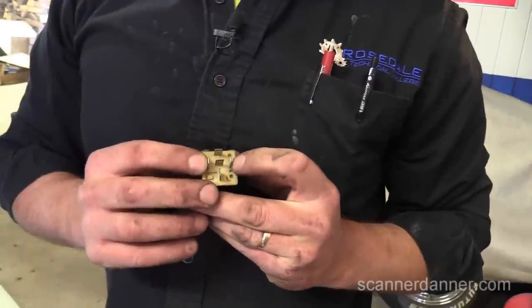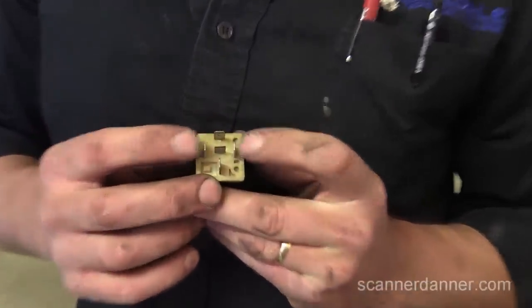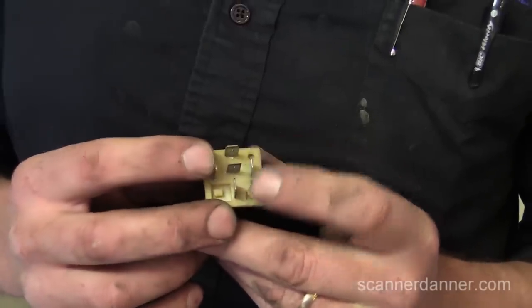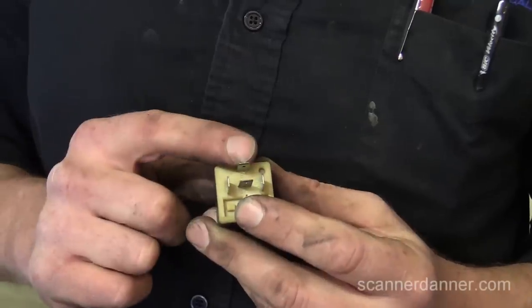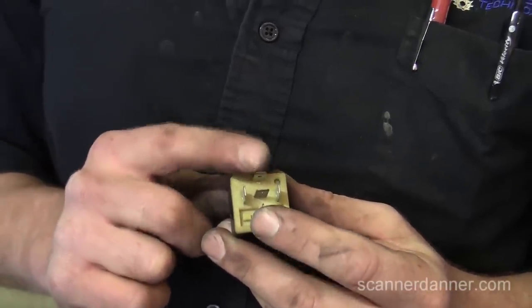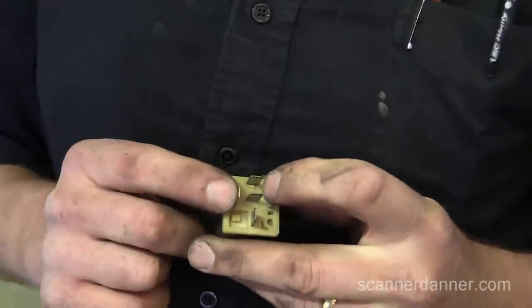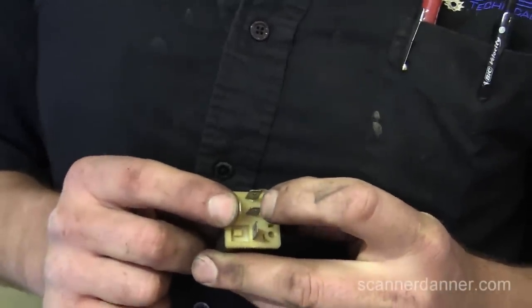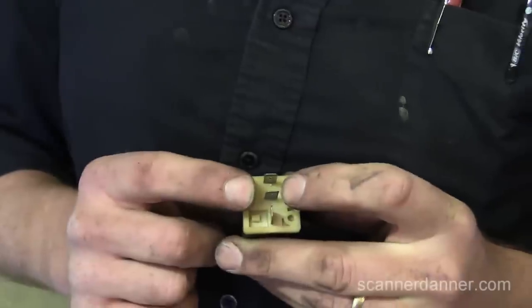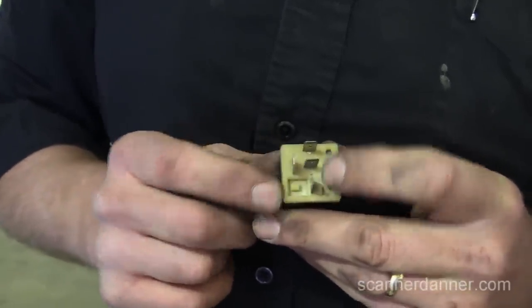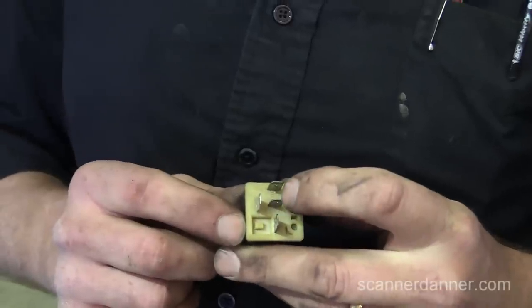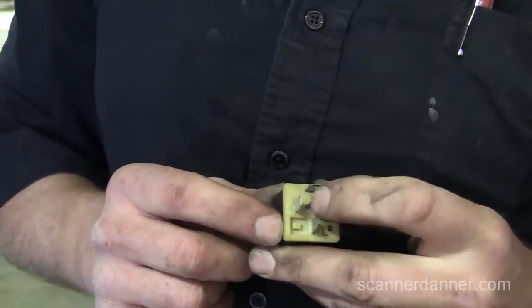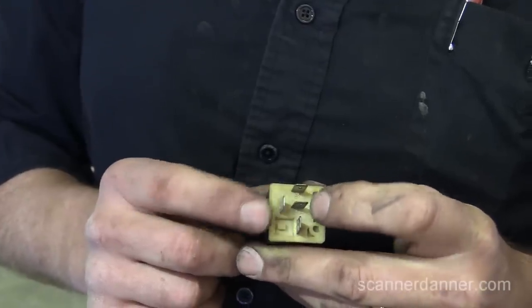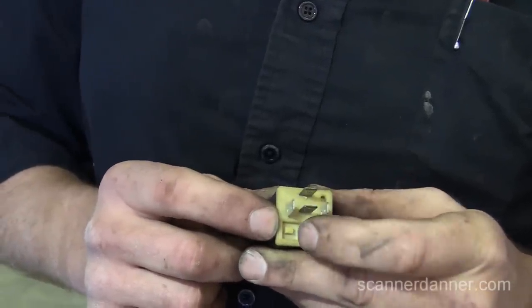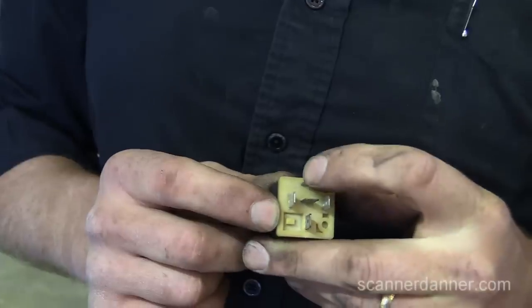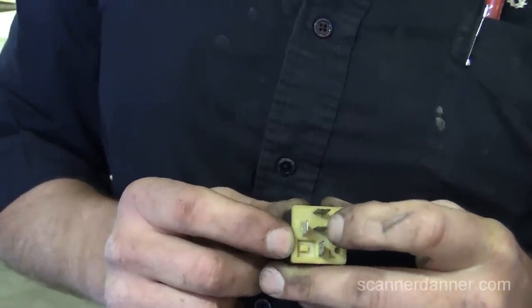On this relay, here's your control coil side, it makes a magnetic field. And when it makes a magnetic field, it connects this terminal to this terminal. These are normally open, load side and control side. This middle pin that's not being used is also a load pin with no coil control, no magnetic field here. This pin and this pin are electrically connected, it's a normally closed contact. When we make a magnetic field here, it opens that contact and closes this one. So this normally closed contact is not being used.